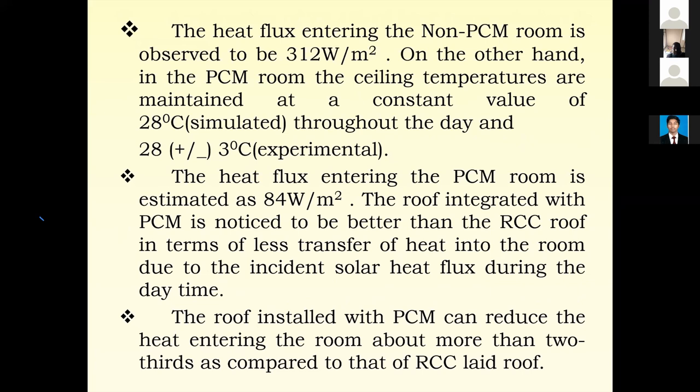That is one way. Secondly, thermal comfort, as we are maintaining temperatures within the comfort range, that is 22 to 35 degrees. If you select a material with a melting point even less than 29 degrees, you can have better inside temperatures. If you select a PCM melting temperature of 22 degrees, you can better maintain 22 or 23 degrees at maximum. It is more convenient, and it gives more comfortable temperature conditions inside the room.